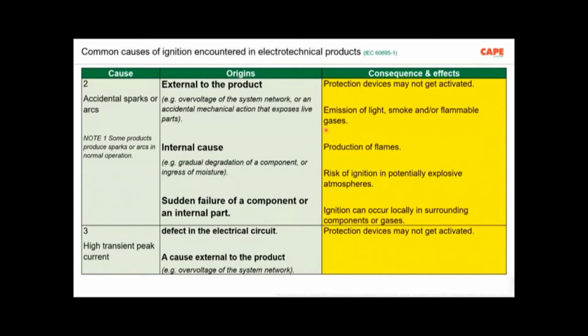Due to overvoltage in the electricity supply, imagine the line to neutral voltage in the electrical system is 230 volt. But due to a fault on the high voltage side of the transformer, the low voltage side can experience a voltage of up to 1200 volt for 5 seconds between each line and the earth, or neutral and the earth. Imagine if your equipment is unable to withstand 1200 volt, of course your equipment will fail and it can create a fire. Number two, this 1200 volt which I mentioned is the maximum limit allowed inside a wiring. This also means the designer, the electricity supply company, has to take care of the transformer in such a way that more than 1200 volt is not allowed inside your electrical installation.